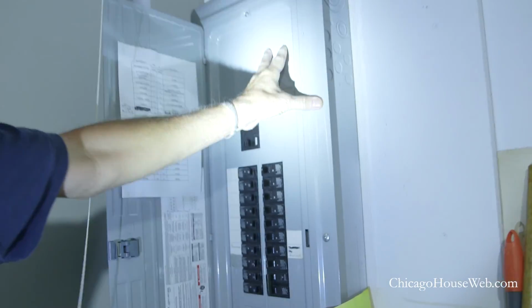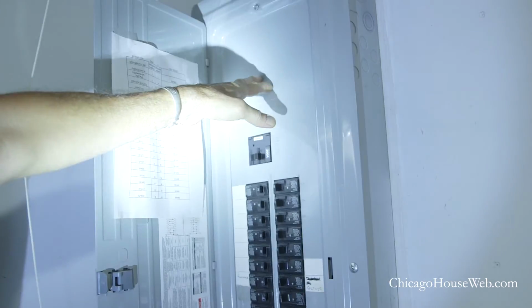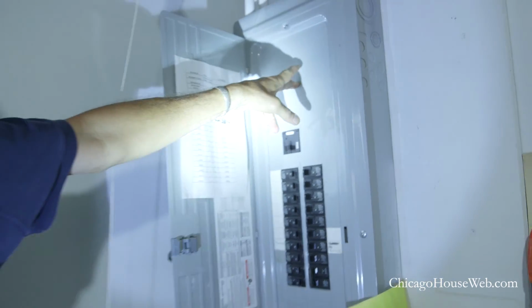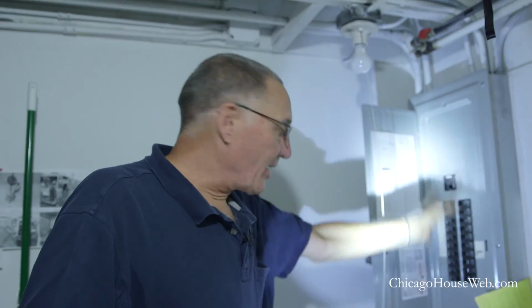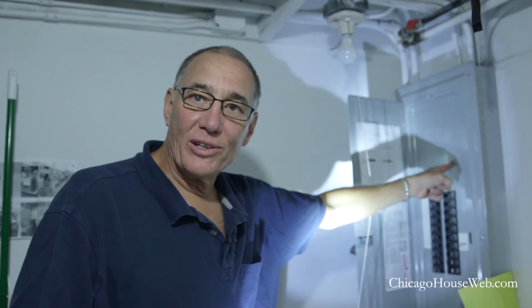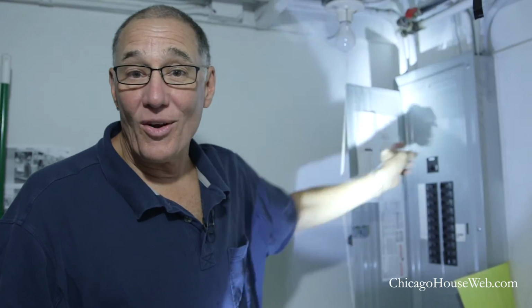I'm not going to take the main cover off, but State of Illinois law requires that the home inspector pull this main panel cover to look inside and check the bonding, grounding, types of wire, and whether the breakers are properly sized for all the various circuits. If they're not pulling this cover off and looking inside, you're not getting a real home inspection.